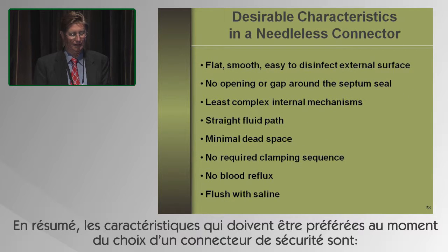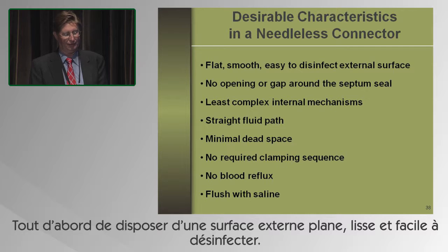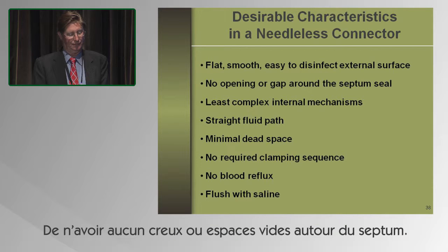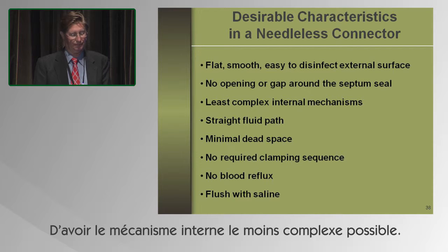So the desirable features that you should look for in a needleless connector are first to have a flat, smooth, easy to disinfect external surface. To have no opening or gap around the sealed septum. To have the least complex internal mechanism.